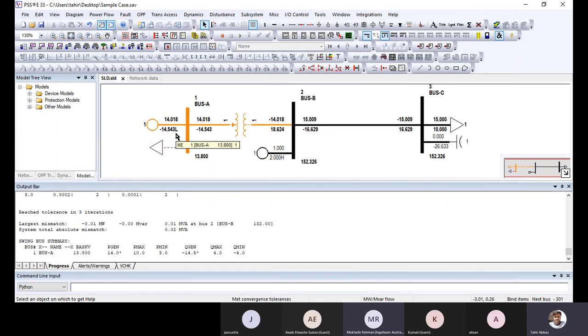This is how PSSE gives you a hint, and this is called reactive balancing. First is the swing balancing, and next is the reactive balancing. So you asked about the swing balancing, and you asked about the reactive balancing, and we will do these exercises in the next case. Whenever we make a case, the first concept is to balance your swing, the next is to reactive balance your generator, and the third is to check your voltage, that there is no limit violation, no voltage violation, then check the under voltage and overvoltage on branches. Then move towards the power flow analysis and the short circuit analysis.